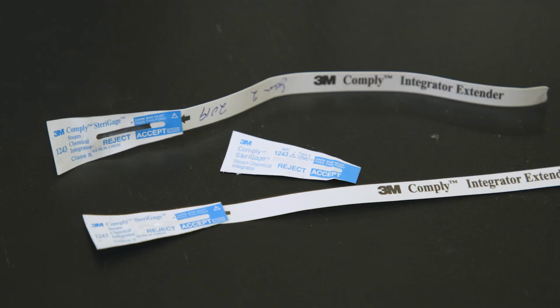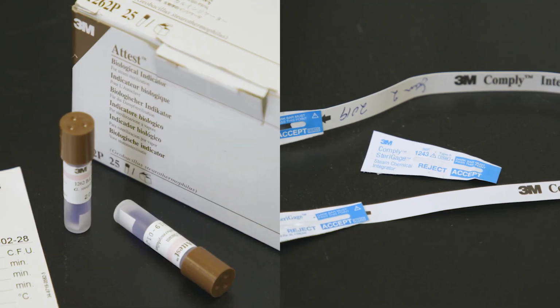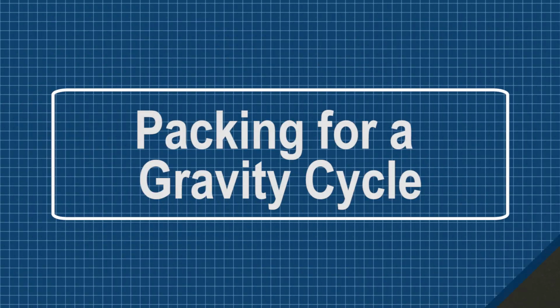Chemical integrator strips and biological indicators, such as spore tests, both verify that the contents of the autoclave have been successfully sterilized or decontaminated by reaching 121 degrees Celsius for a given period of time. Now let's look at how to package some of the common items that you would run through a gravity cycle.